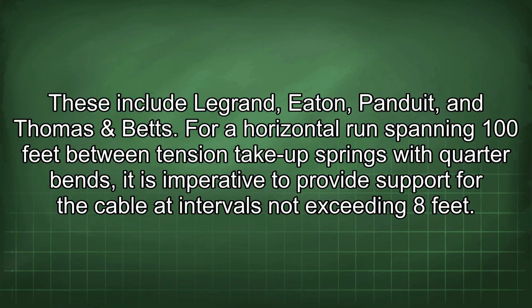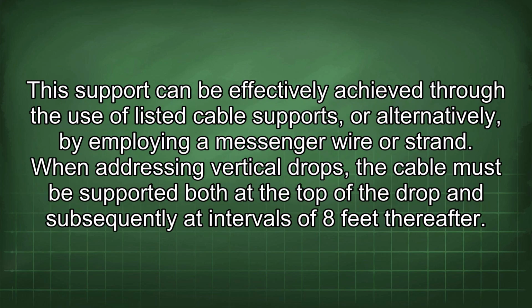For a horizontal run spanning 100 feet between tension take-up springs with quarter bends, it is imperative to provide support for the cable at intervals not exceeding 8 feet. This support can be effectively achieved through the use of listed cable supports, or alternatively, by employing a messenger wire or strand. When addressing vertical drops, the cable must be supported both at the top of the drop and subsequently at intervals of 8 feet thereafter.